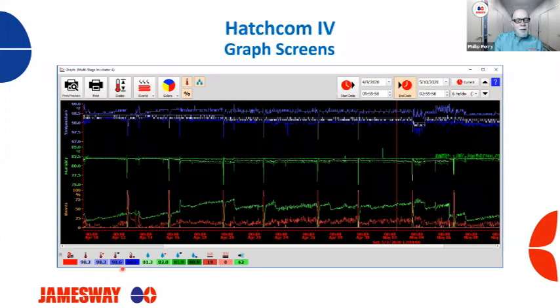My high was 98.6 and my low looks like 98 degrees. So very, very large temperature swings here, probably going into alarm occasionally. But anyway, when I reported that there's an issue with this machine, they went back and looked, and the solid state relay was stuck on. So for the heater element.